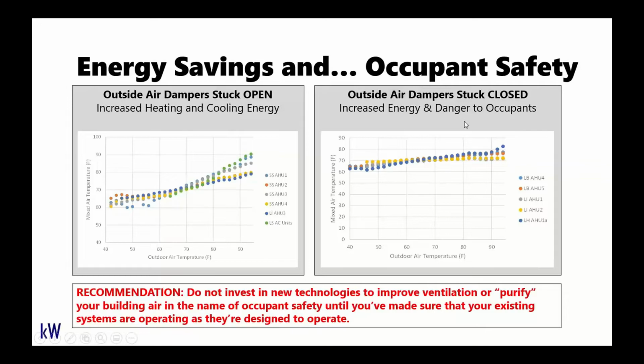So the outside air damper being stuck closed, that's actually going to help with the heating and cooling loads maybe at these extreme temperatures. But as we're all well aware of right now, ventilation is very important. And having these dampers stuck closed essentially means that the occupants in these areas that are served by the air handlers are not getting the outside airflow rate that is intended and required by the design of the system.